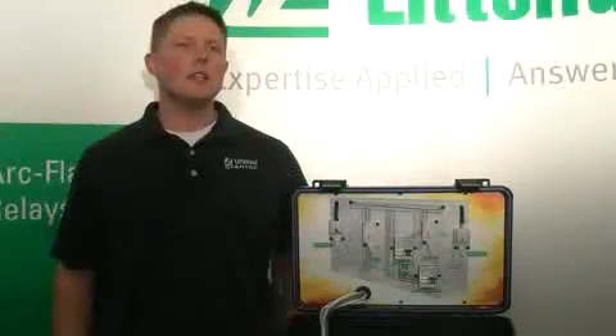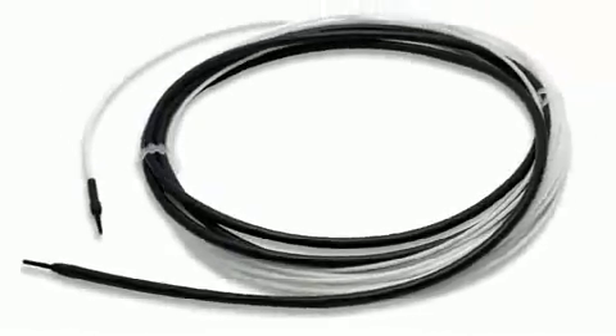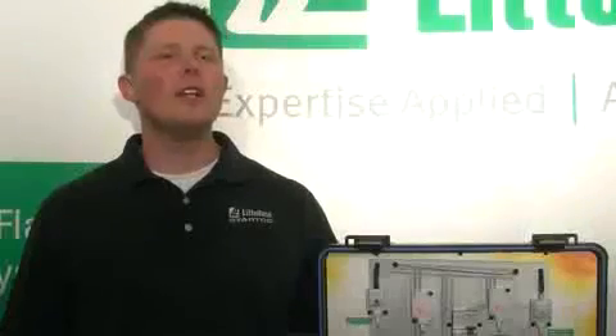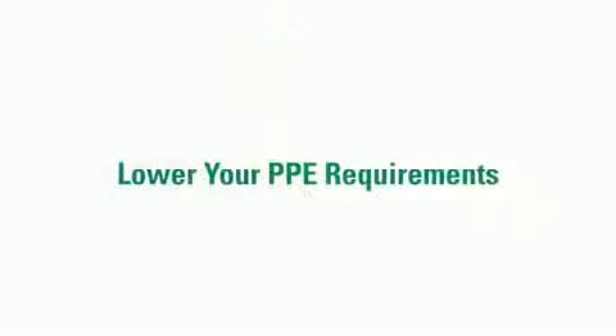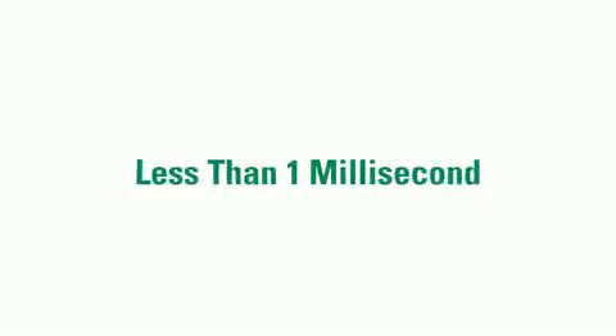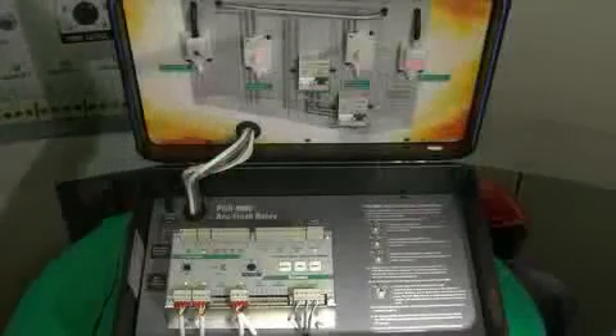An arc flash relay is a relay that uses sensors to visually see an arc and send a trip signal to a shunt trip breaker upstream. An arc flash relay can lower PPE requirements by seeing the flash and sending the trip signal in less than 1 millisecond. This is our PGR 8800 arc flash demo case.